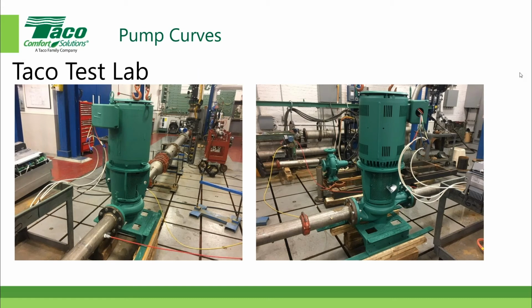But you can see a little bit more information in terms of how we make our connections for our instrumentation. This blue guy way back here on this pipe is where we measure the flow in gallons per minute. This yellow pipe is measuring the suction pressure. This red pipe is measuring the discharge pressure. And because this is for certification, we're not measuring the actual power input to the pump shaft. We're measuring the total electrical power input and correcting for the motor efficiency.